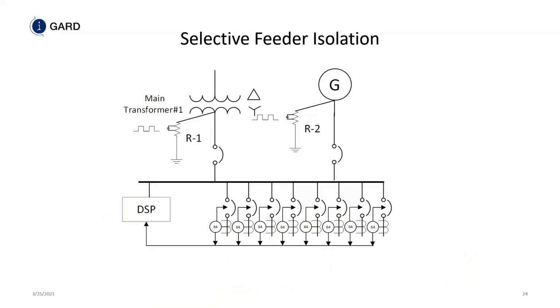So in this particular example, we have a full-blown smart HRG system. So I could have a fault over here, and I can say that that fault is on feeder 6. So already I start the pulsing. I could start my pulsing at feeder number 6. If you had a conventional HRG system, you would actually start the pulsing, determine which breaker was closed, and then start looking here for where your fault is, or here.